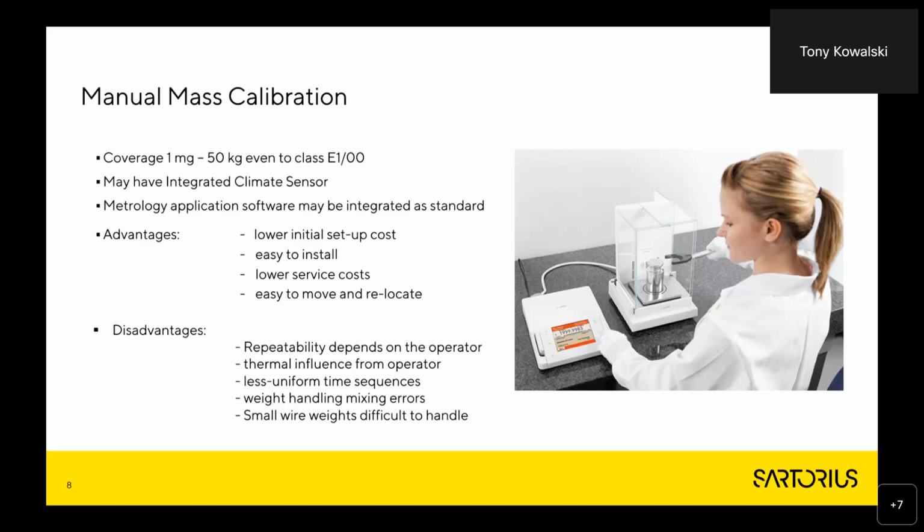If you change your laboratory or you want to move the mass comparator, generally there's nothing difficult, no adjusting of the weighing system for transport. You simply switch off, move the comparator, and relocate it to the new position. So there are the advantages.